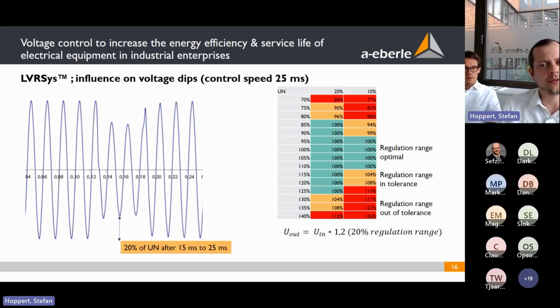Jumping to the influence of voltage dips. Of course, our system has a control speed of 15 to 25 milliseconds. But what does that mean for voltage dips? Because of the principle, and I jump to the calculation on the right side, the output voltage is dependent on the input voltage, and we can regulate and add to the input voltage in percentage steps. That means if we are talking about a system which could raise the voltage by 20%, we have to multiply this 20% with the input voltage. If we go to the table on the right, if the incoming voltage, the UN, the nominal voltage, goes down to 70%, multiplied by 1.2, we can reach an output voltage of 84%.